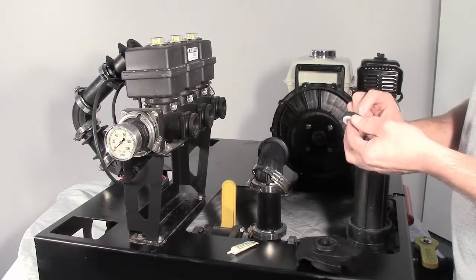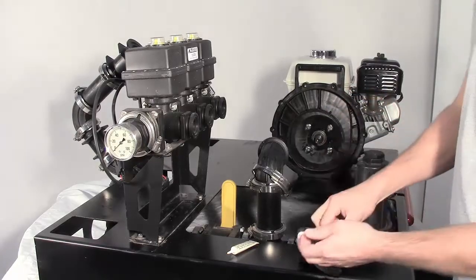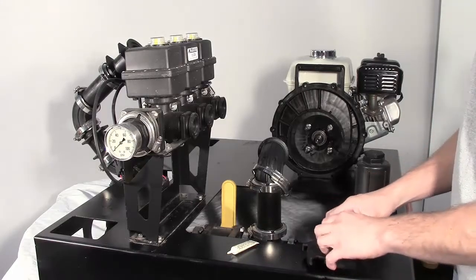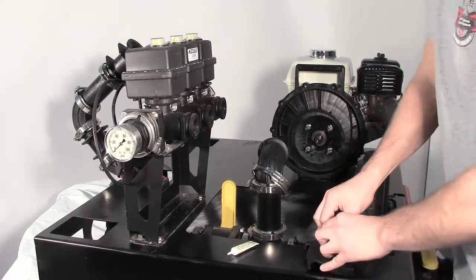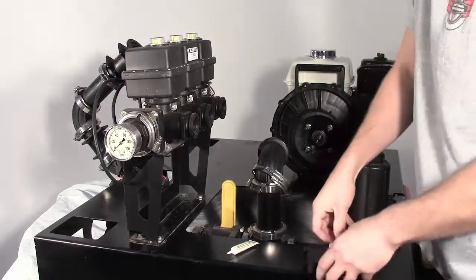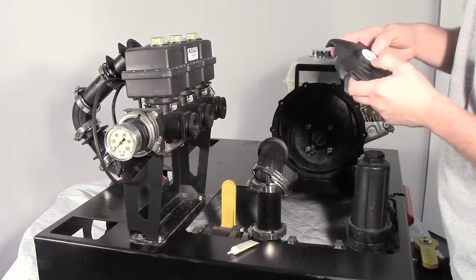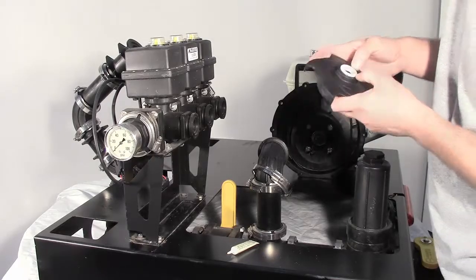Ensure that the white ceramic seal surface is facing outward when inserting into the impeller hub. Be absolutely sure that the ceramic seal half is bottomed out and installed squarely. If the installation is not square, seal wobble will occur leading to premature seal failure.